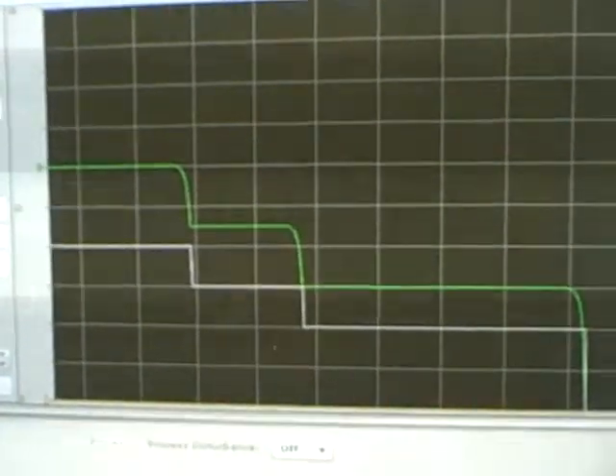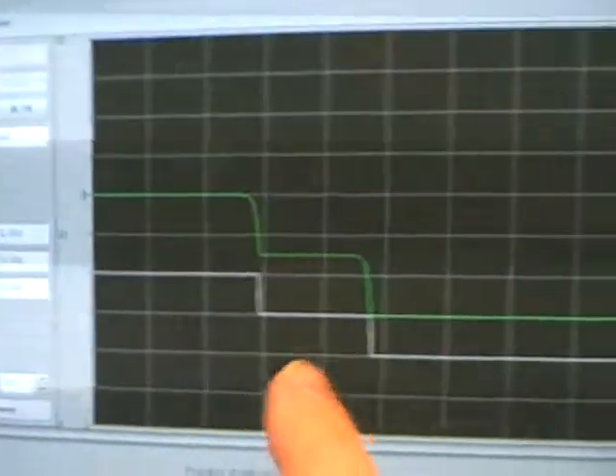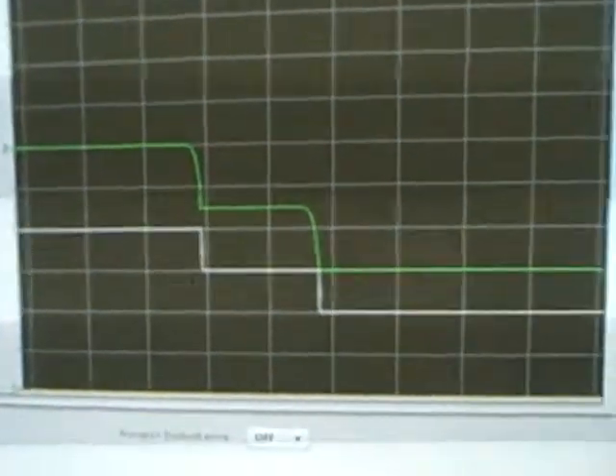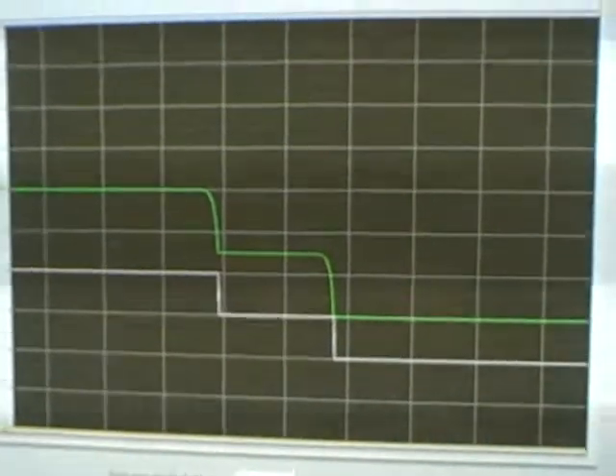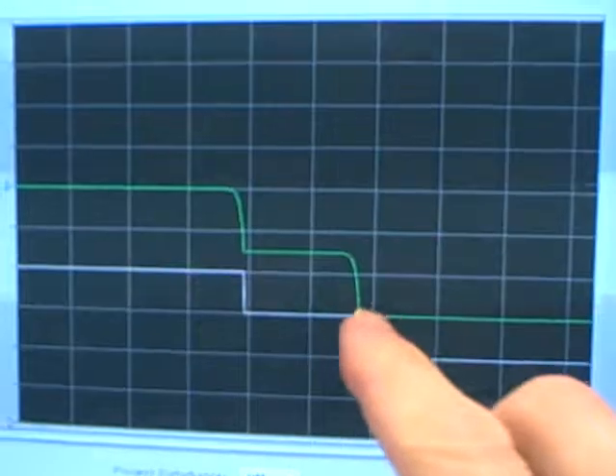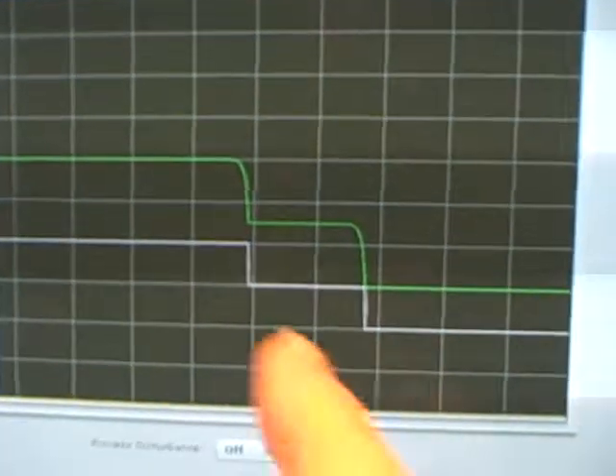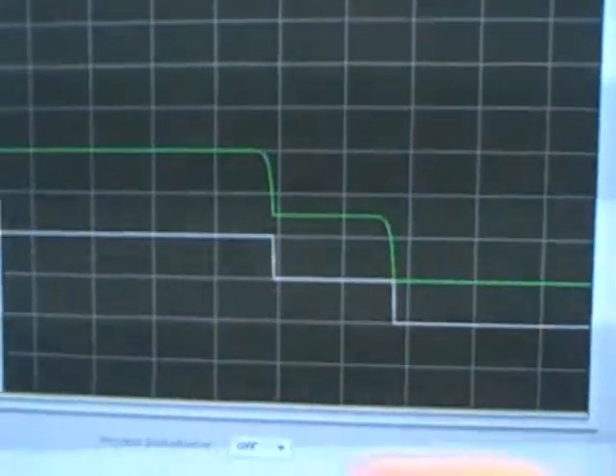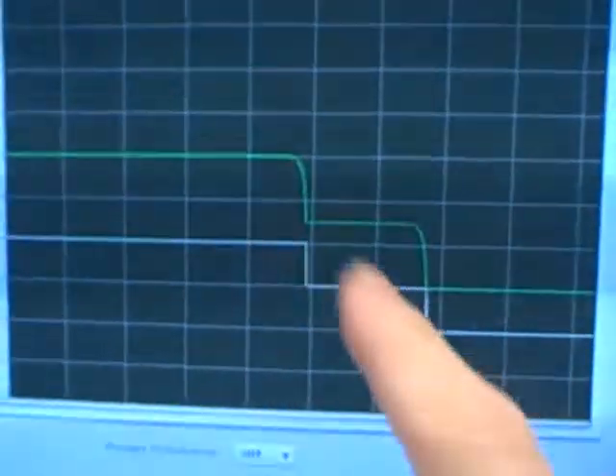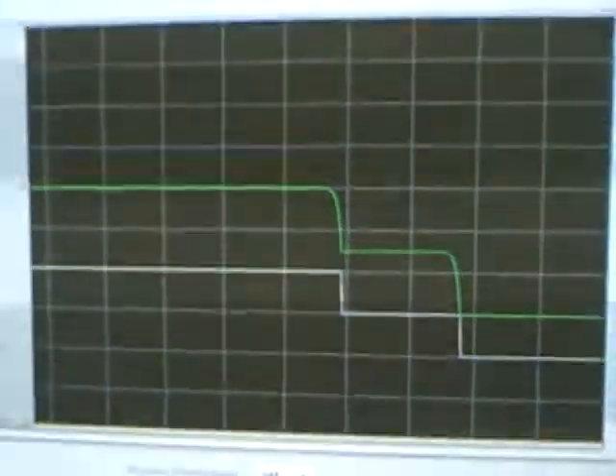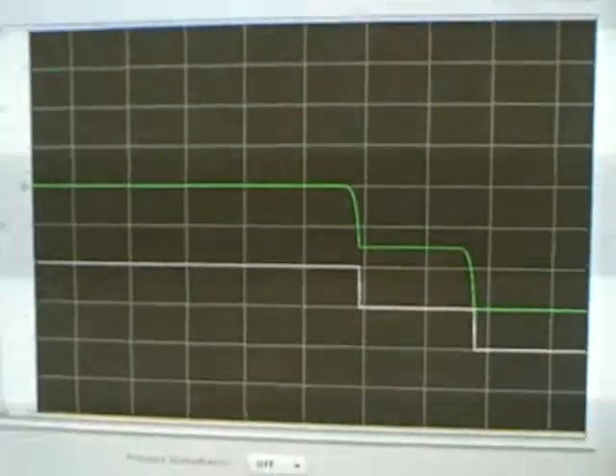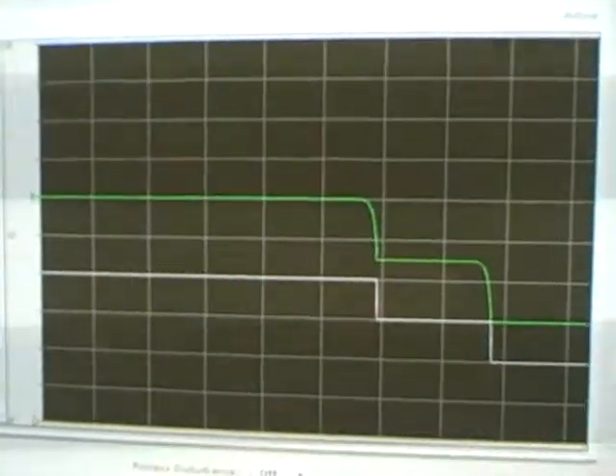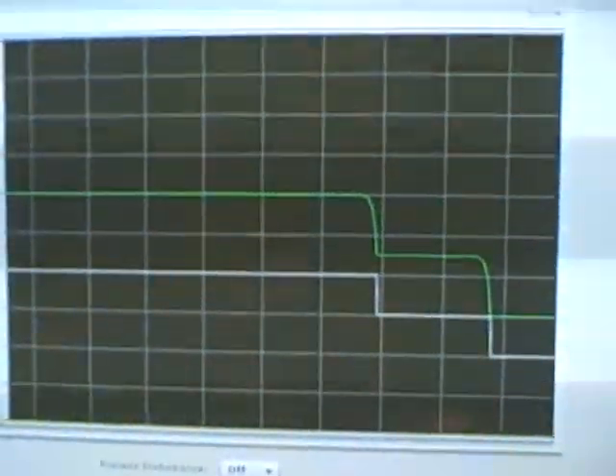The question then becomes, what tuning parameters should we use in our controller to yield good control from this process? Well, being that it's a self-regulating process, the process itself requires a new valve position for every new process variable value that we wish to achieve. We can see this very clearly on the trend through our open-loop step changes. In order to get the process variable to some new value, we require a novel valve position. There's really only one control action that can possibly do this, and that is integral action. Only integral action is able to generate brand new valve positions to get us to brand new set point values.